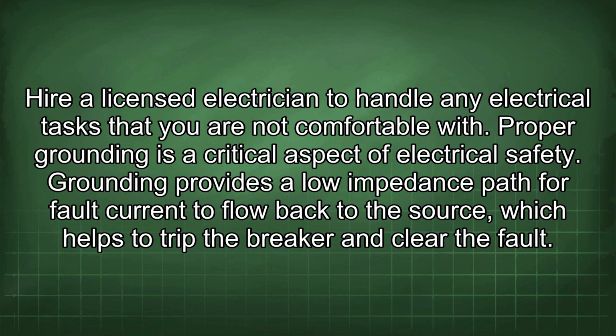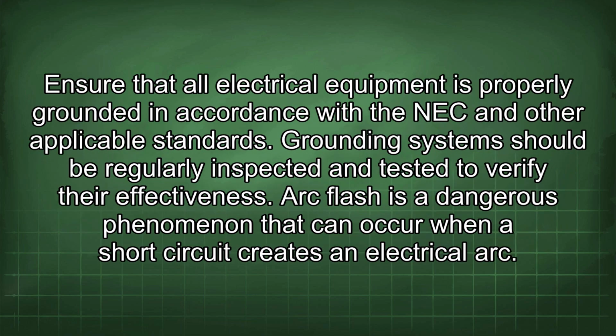Proper grounding is a critical aspect of electrical safety. Grounding provides a low impedance path for fault current to flow back to the source, which helps to trip the breaker and clear the fault. Ensure that all electrical equipment is properly grounded in accordance with the NEC and other applicable standards. Grounding systems should be regularly inspected and tested to verify their effectiveness.